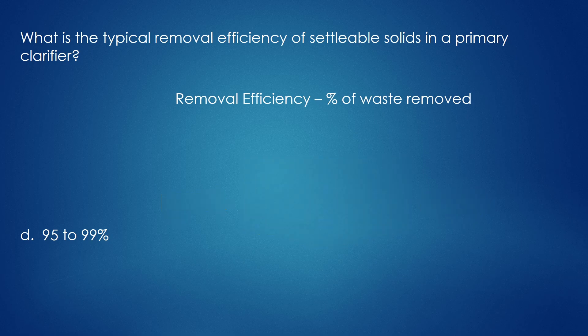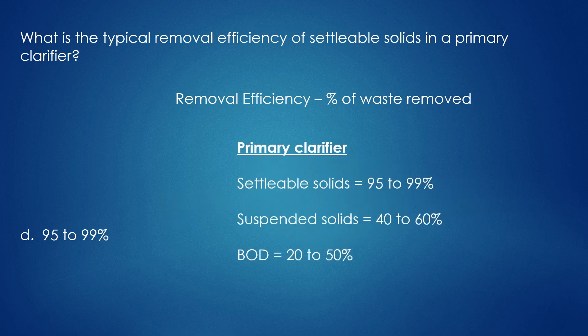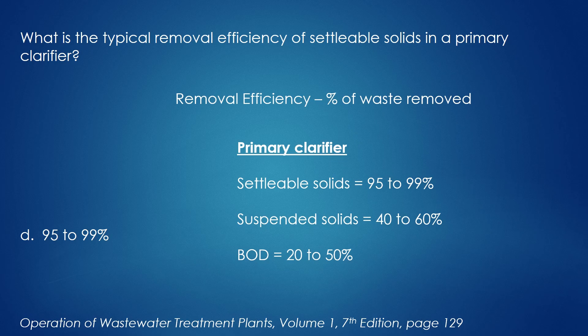Other common removal efficiencies you should know for the primary clarifier are suspended solids at 40-60%, and BOD at 20-50%. To learn more, go to the textbook Operation of Wastewater Treatment Plants Volume 1, page 129, where they go over it in more detail.